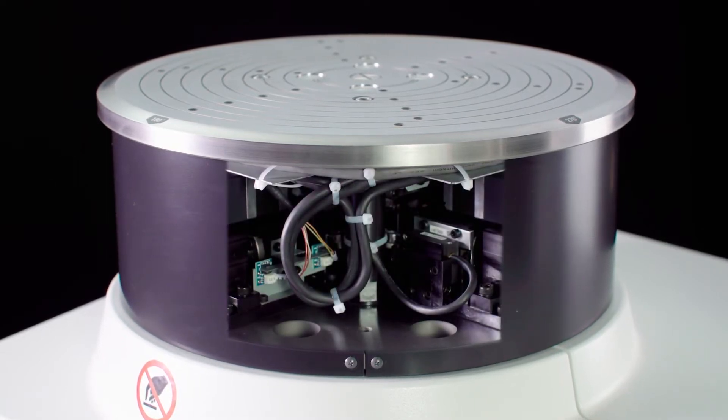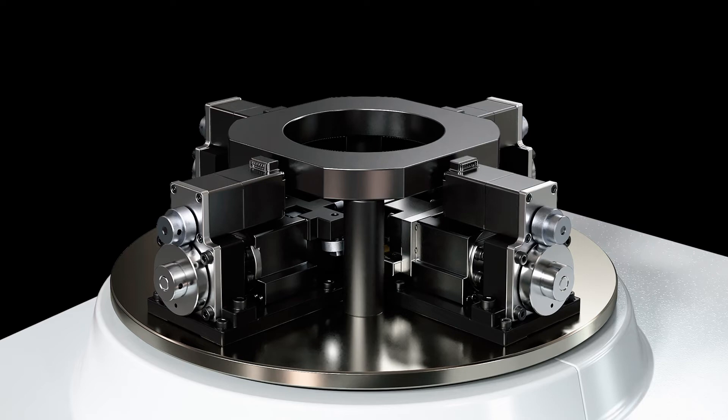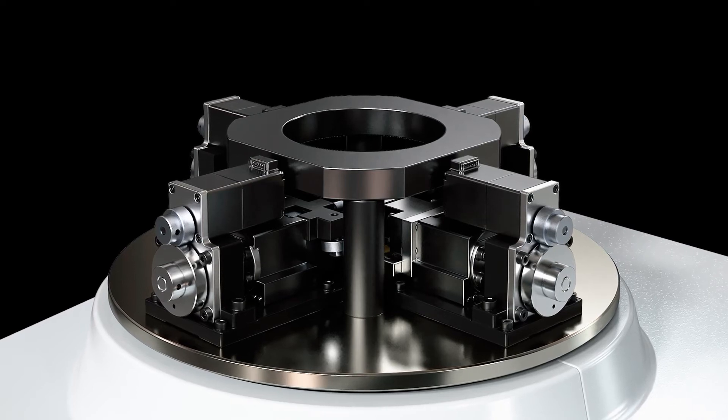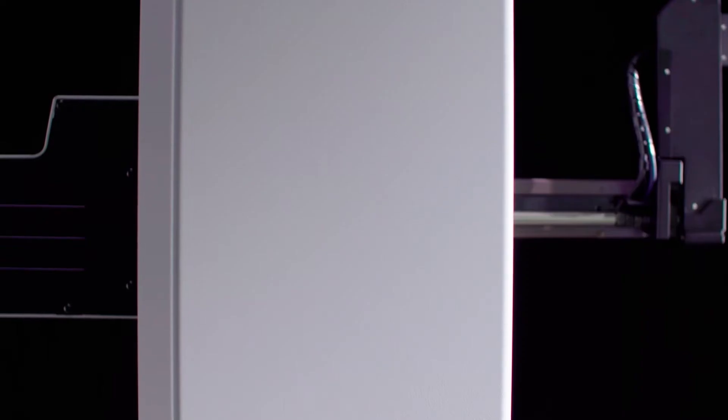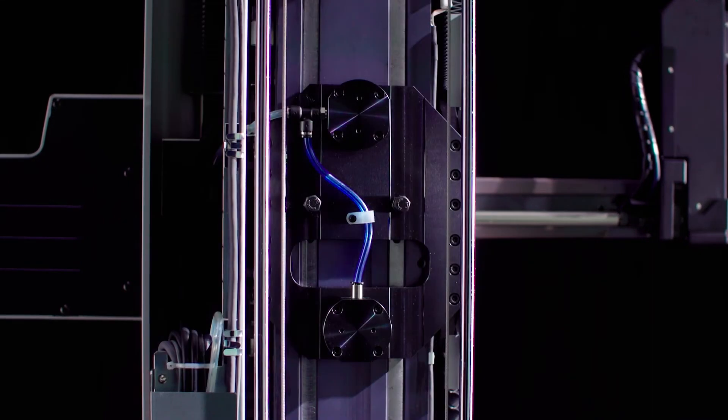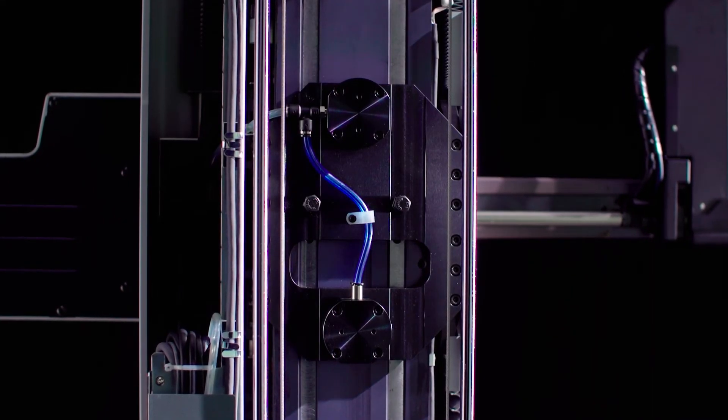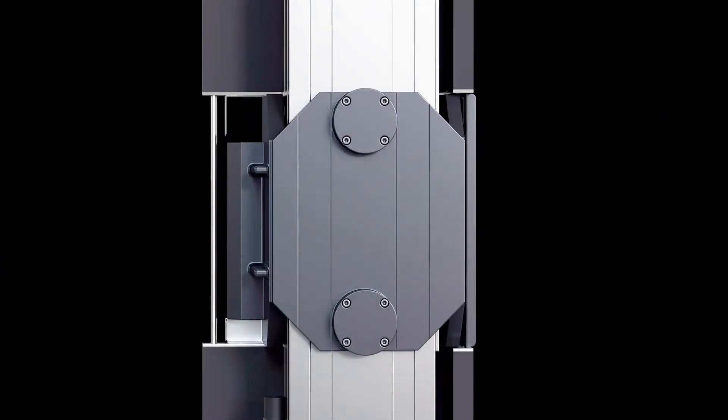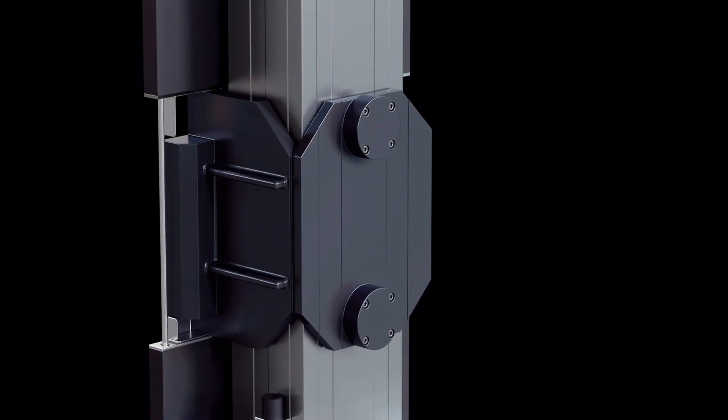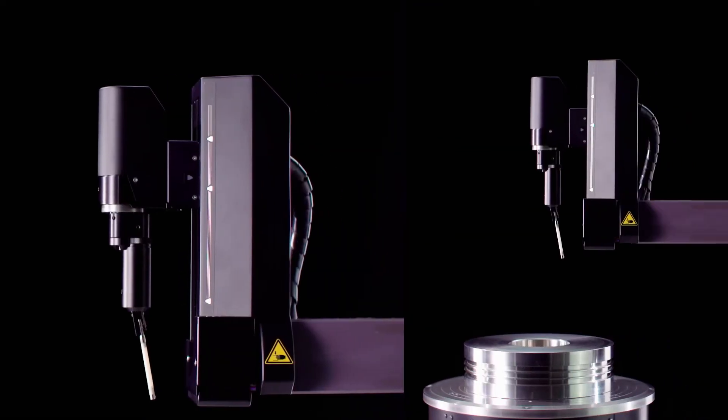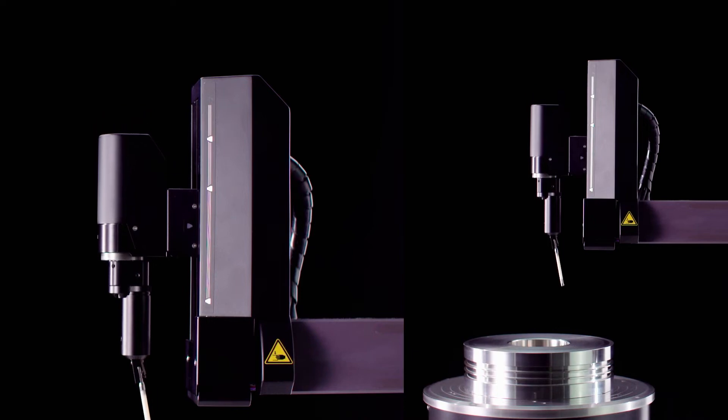New internal architecture of the rotary table reduces the positional changes of the workpiece during measurement which results in improved reproducibility. A new design column Z axis slider consisting of a friction guide and air bearings is resistant to vibration resulting in improved positioning accuracy. These redesigns greatly improve the repeatability of the measurements.